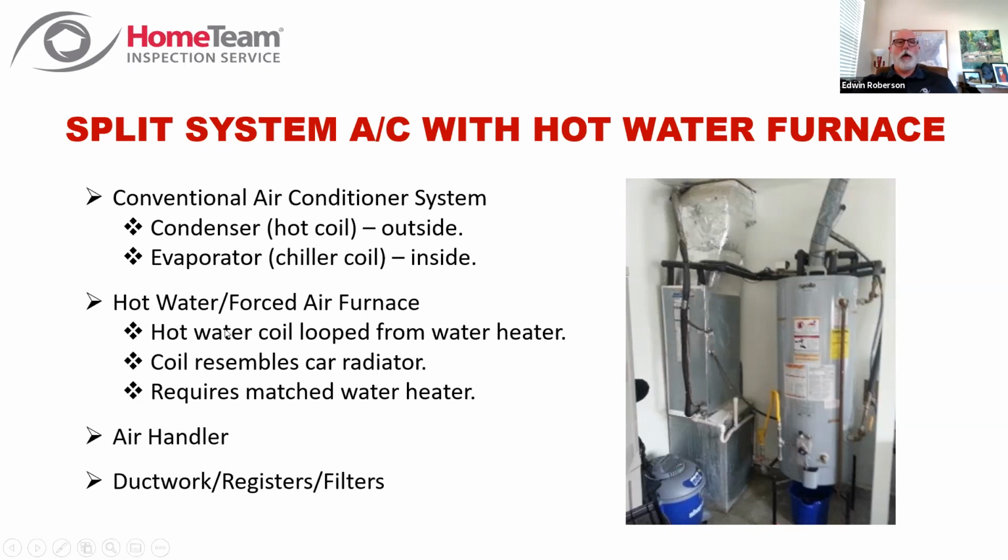And the way that works is you have to have what's called an Apollo type water heater, and many manufacturers make them. This one happens to be an Apollo; you can see its label. But what you've got, and let me minimize this so I can point here to you, if you'll notice in this water heater, you've got your normal hot and cold water lines in and out of the top of this, like every other water heater. But in addition, you've got these other two inlet and outlet lines.